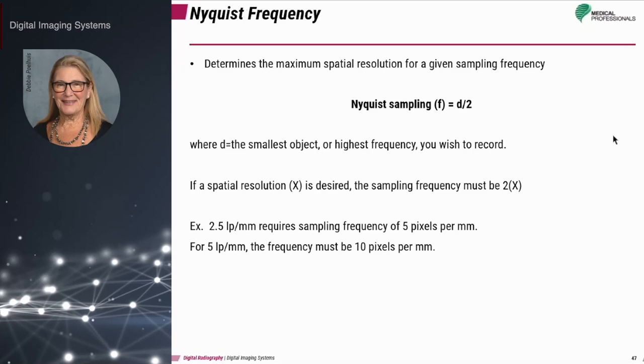The Nyquist theorem applies to CR imaging. The Nyquist frequency determines the maximum spatial resolution for a given sample frequency. The theorem states that if a certain spatial resolution is desired, the sampling frequency must be two times that. For example, a 2.5 line pair per millimeter resolution requires a sampling frequency of 5 pixels per millimeter; a spatial resolution of 5 line pairs per millimeter requires a sampling frequency of 10 pixels per millimeter.